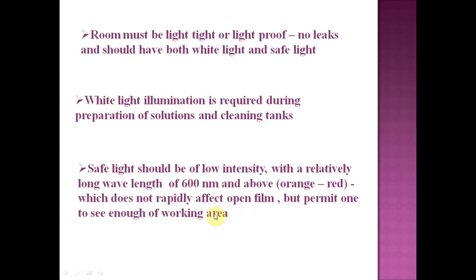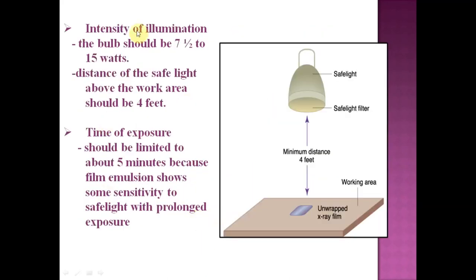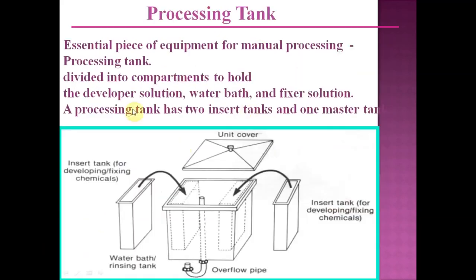White light is required during preparation of solutions and cleaning of tanks. The safe light should be of low intensity with a relatively long wavelength of 600 nanometers and above, in the orange-red region of the spectrum. The bulb should be 7.5 to 15 watts, the distance of the safe light above the working area should be at least four feet from the film, and the time of exposure should be limited to about five minutes, since film emulsion shows some sensitivity to safe light with prolonged exposure.